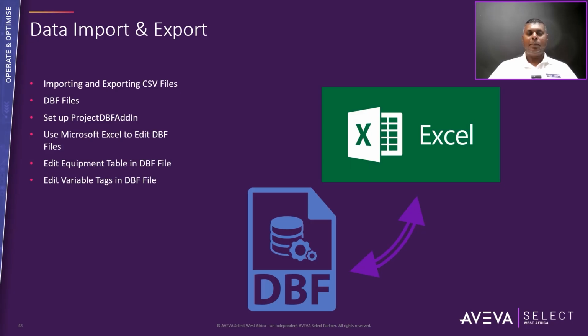Data import and export. Most of the Plant SCADA configuration data is stored in DBF files. DBF files are database files originally developed to be used by the data management software called dBASE. In general, the Plant SCADA Studio data represented in the grid editor are stored in its own DBF files. These DBF files are found in the project directory and can be manipulated external to the Plant SCADA Studio. In order to use the DBF files, please ensure to add in the Project DBF add-in to your Excel.